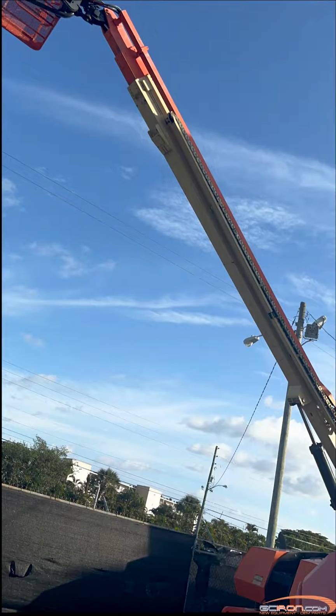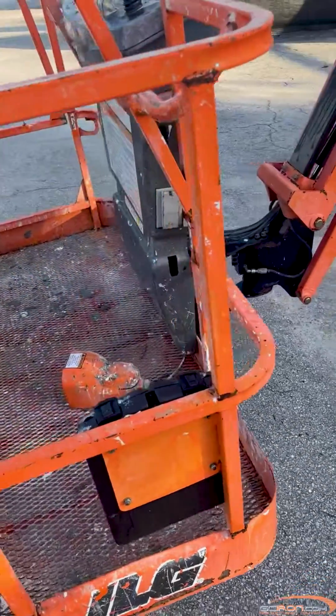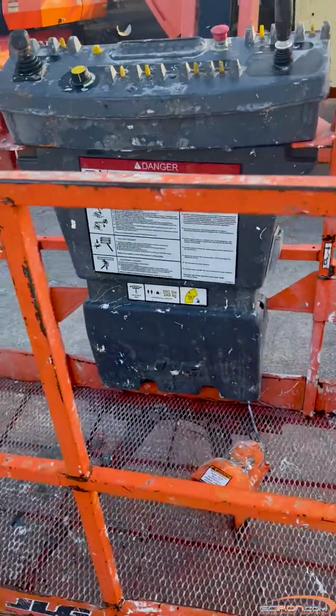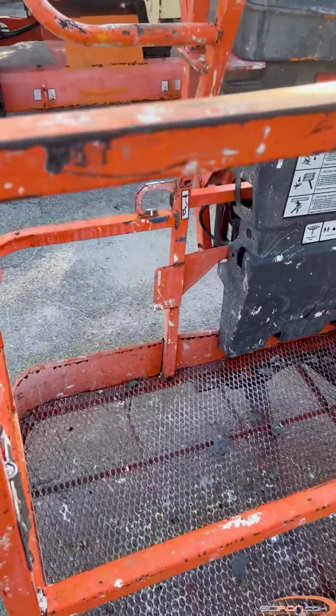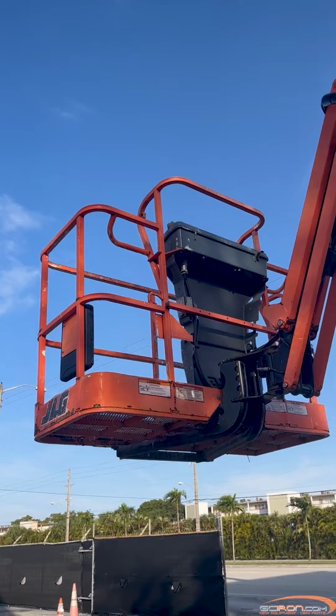Using the JLG analyzer, scroll through the following menus to the menu item at the end. The menu item should read as stated beside it. Diagnostics, boom functions. Verify that all boom function outputs are showing 0%.